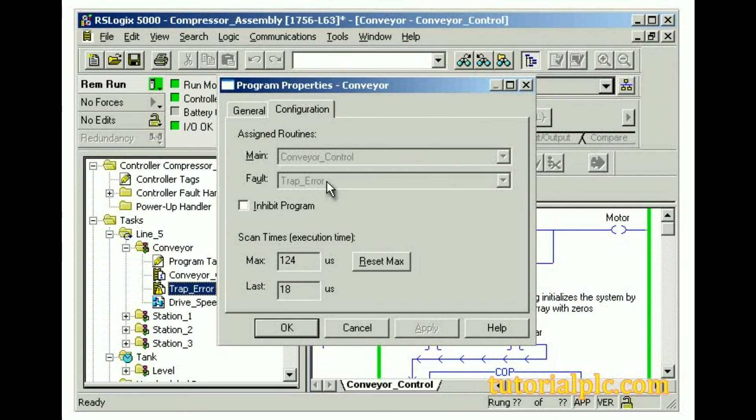If a fault is cleared by the fault routine, the ladder program continues executing at the instruction immediately after the instruction that caused the program fault, and the controller does not enter fault mode.